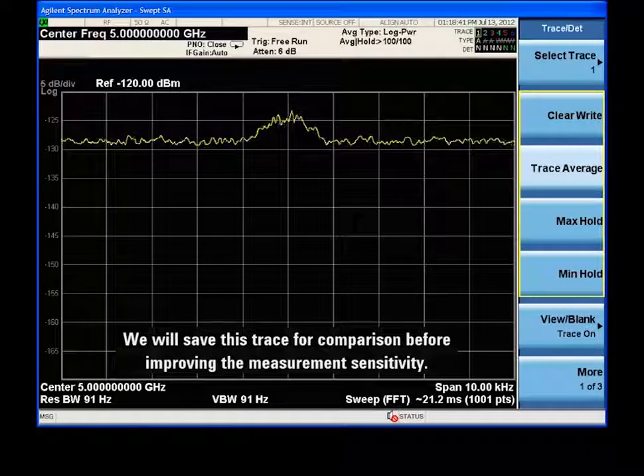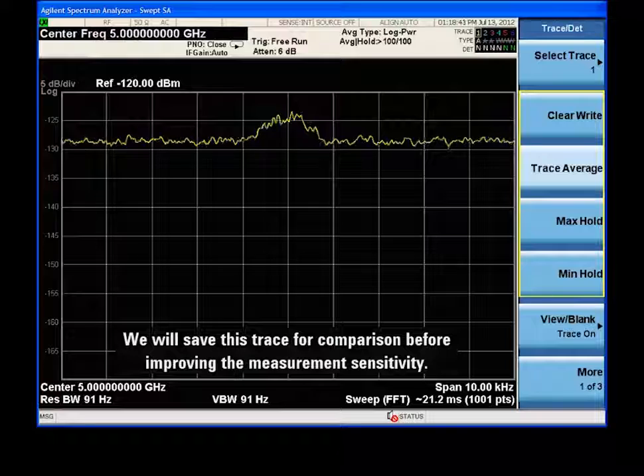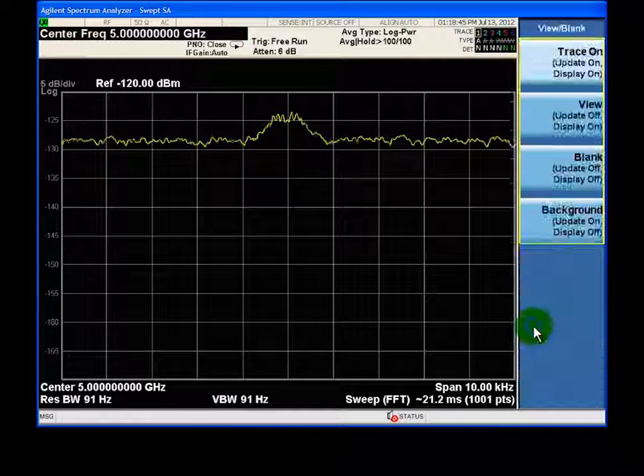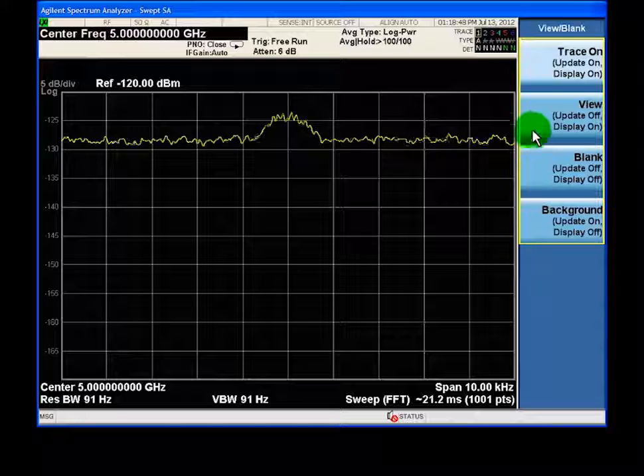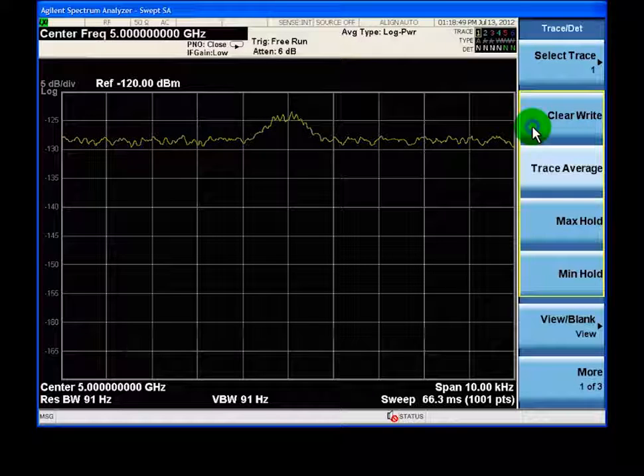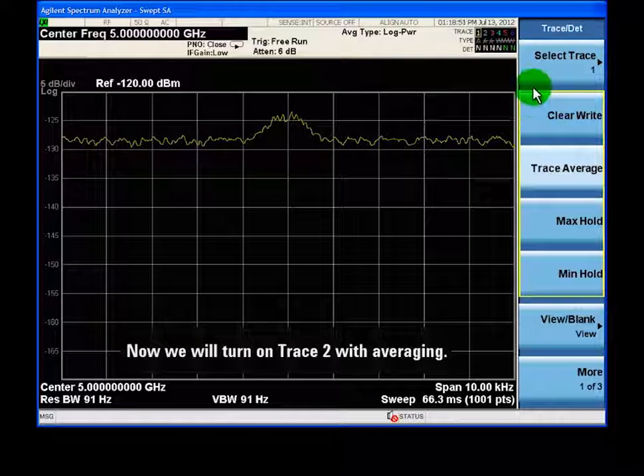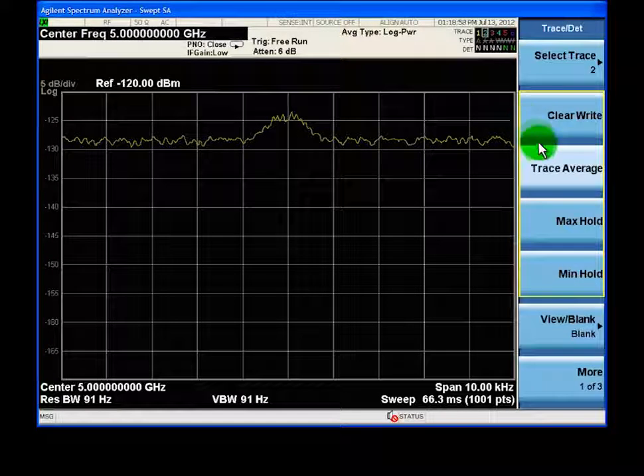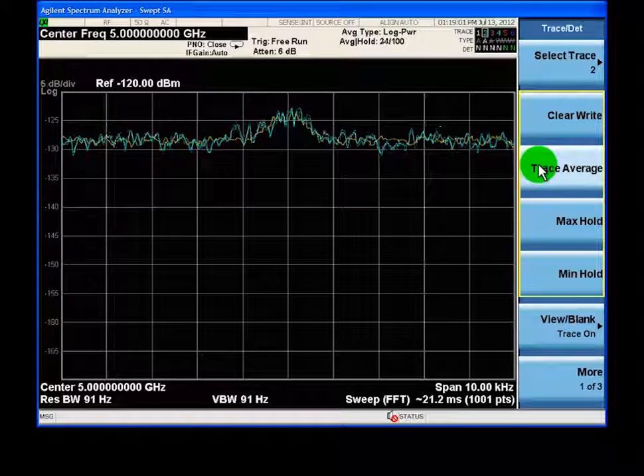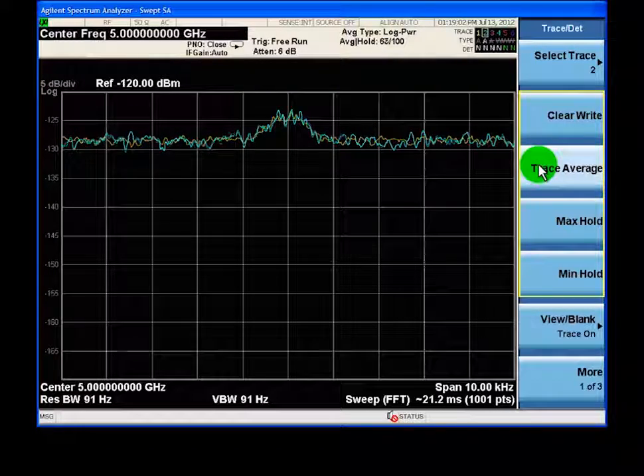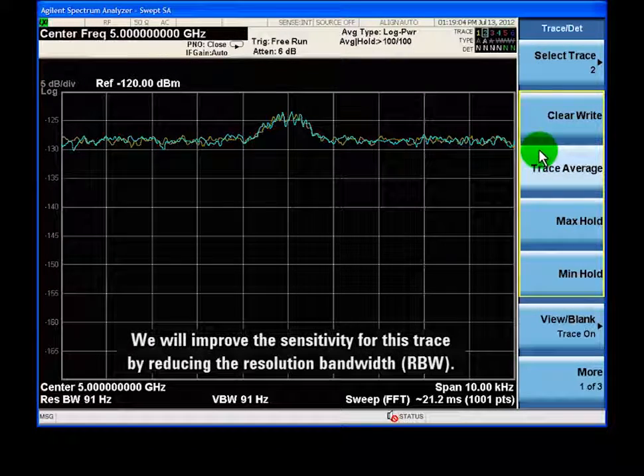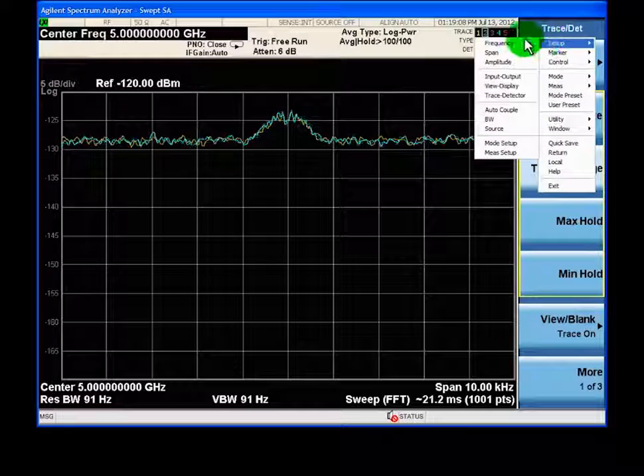We'll save this trace for comparison before improving the measurement sensitivity. Now we'll turn on trace 2 with averaging. On this trace, we'll improve the sensitivity by reducing the resolution bandwidth.